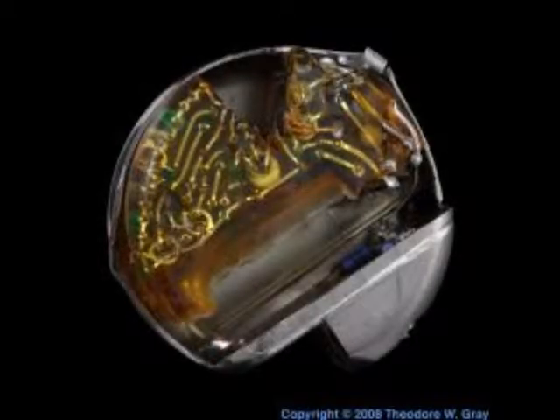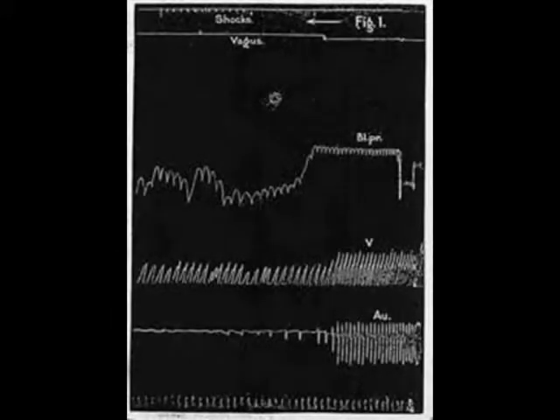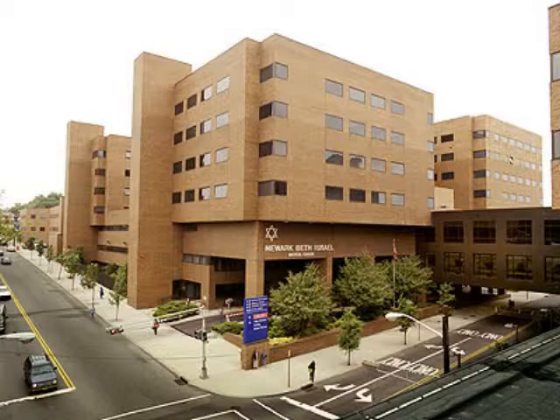The nuclear device, which weighed 3½ ounces and was about two-thirds of the size of a pack of cigarettes, was developed by the Atomic Energy Commission with the Nuclear Materials and Equipment Corporation of Apollo, Pennsylvania. The radioactive plutonium is housed in a case that looks like a small film roller. Attached to the roller are six pairs of tapes called thermocouples, which convert the heat generated by the radioactive source into electrical energy. The resulting current runs into a tiny electronics unit, which produces the pulse that stimulates the heart to beat. The disadvantages were that recipients were unable to leave the country and it did not have diagnostic capabilities — this pacemaker only made the heart beat.